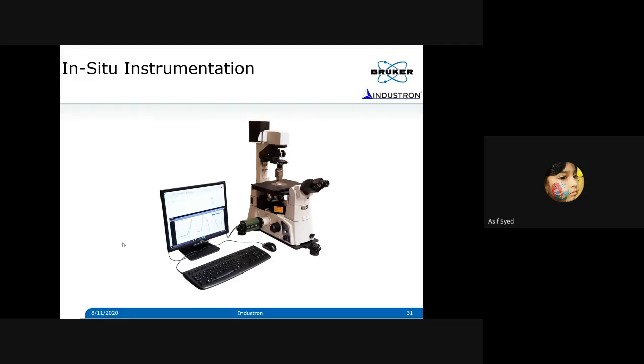And you can use this optical microscope and all the optical microscopic capability, like for example phase contrast imaging or fluorescent imaging. You can use all of that to see the cells or the sites that you wanted to understand. And then you can see here there is a transducer hanging down on the condenser part. That is the part that we developed. This is a unique transducer which has, I'm going to tell you more on this. And you can put that on a biological microscope, and then you can use the whole instrument now, not only to see what you wanted to see in a biological system, but you can also do the experiments that we were able to do on hard materials very precisely. That is what this instrumentation is about.